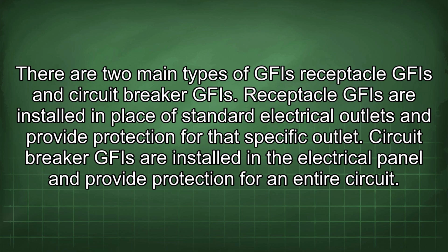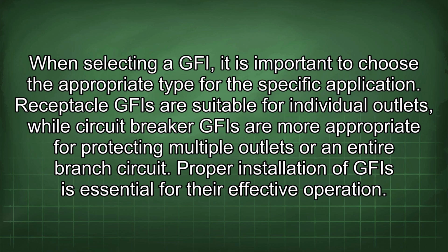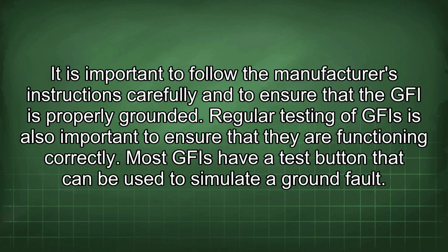Receptacle GFI are installed in place of standard electrical outlets and provide protection for the specific outlet. Circuit breaker GFI are installed in the electrical panel and provide protection for an entire circuit. When selecting a GFI, it is important to choose the appropriate type for the specific application. Receptacle GFI are suitable for individual outlets, while circuit breaker GFI are more appropriate for protecting multiple outlets or an entire branch circuit. Proper installation of GFI is essential for their effective operation. It is important to follow the manufacturer's instructions carefully and to ensure that the GFI is properly grounded.